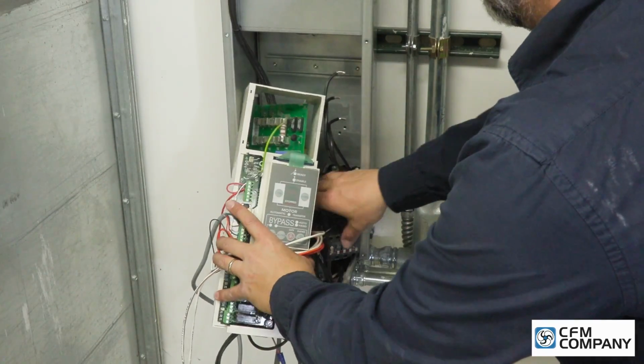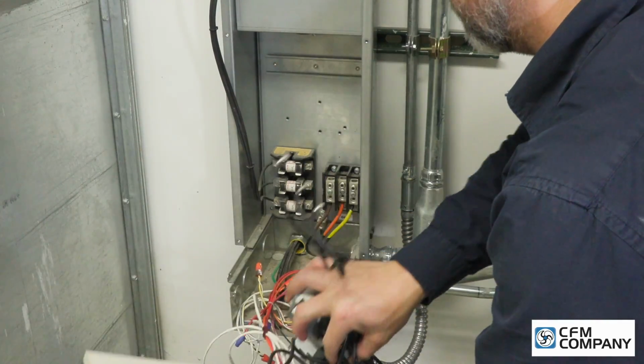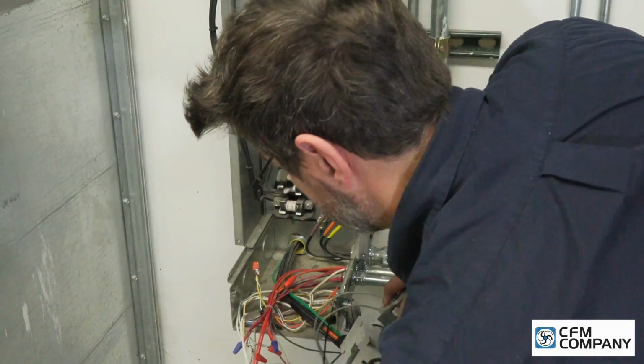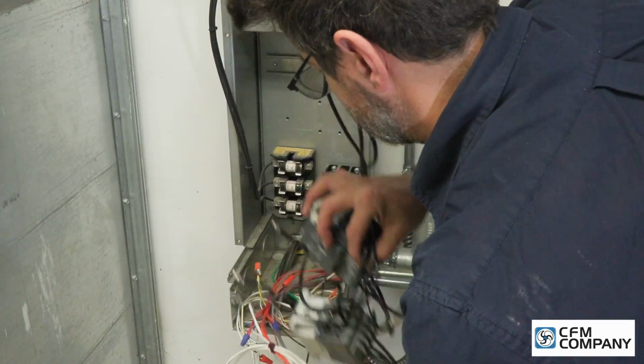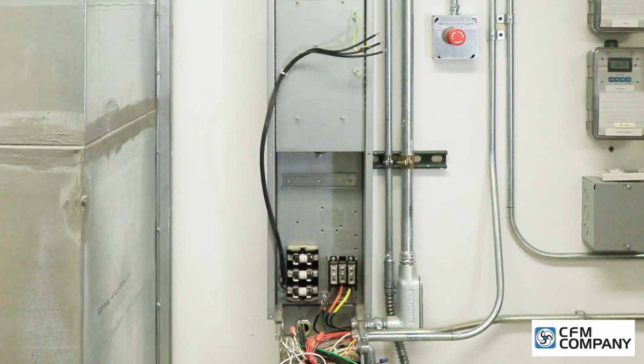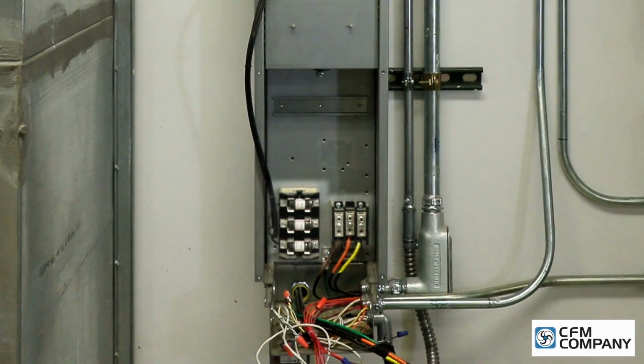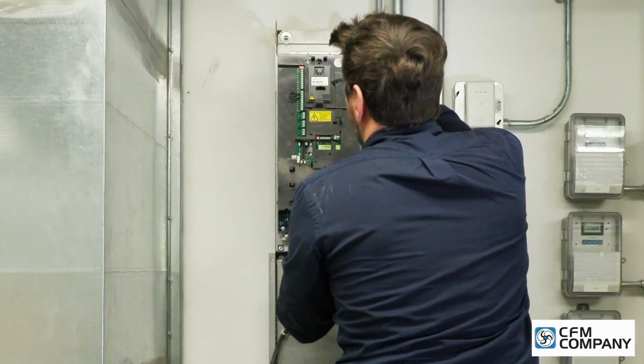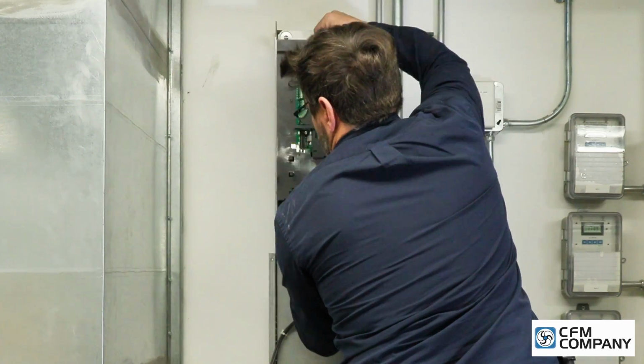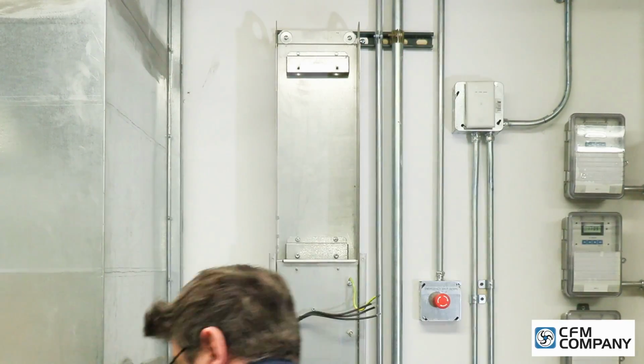All of the components for the bypass can be removed from the drive enclosure. Keep in mind that the control wires are still connected to the bypass control board. With all the bypass components removed, the fuse block and motor terminal block are all that remain. Last of all, remove the original ABB drive. In our example, this is an ACH580 drive.